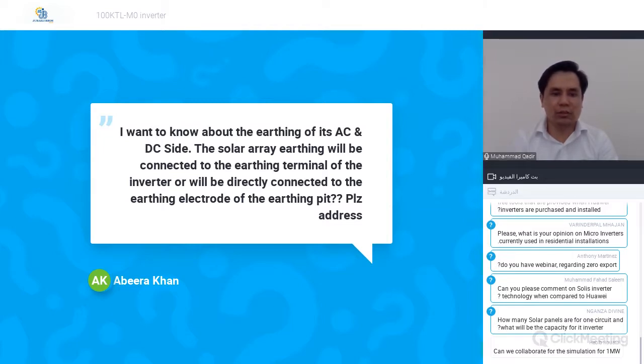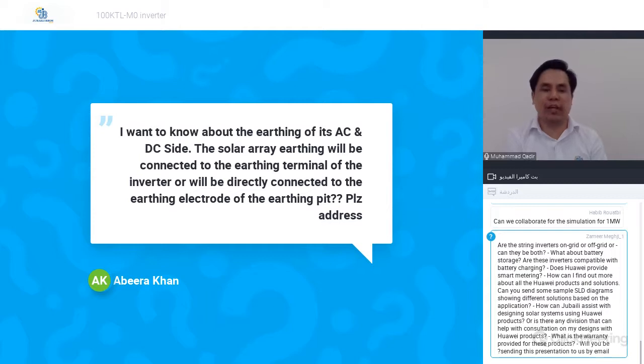There is a question: I want to know about the earthing of its AC and DC side. Will the solar array earthing be connected to the earthing terminal of the inverter or directly connected to the earthing electrode of the earthing pit? Please address. So Huawei advises to have two separate earth pits for the AC and DC side. So you are not going to be terminating your PV frame earthing to the inverter. Rather, you should go to a separate earth pit. Yes, you can do the daisy chain of the inverter earthing and terminate it to the LV panel earthing. But for the frames, you need to have a separate earthing. I hope this clarifies your question.